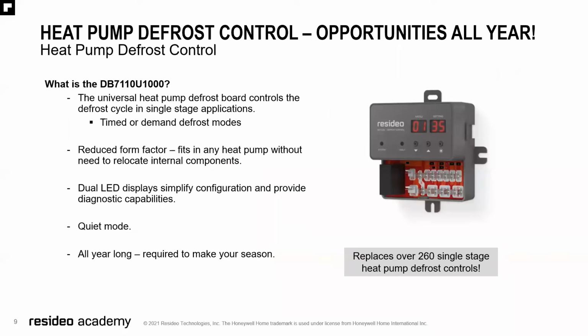Heat pump defrost control. What is the DB7110U 1000? It's a universal heat pump defrost board, controls the defrost cycle of a single stage application, can be timed or demand defrost, reduces form factor, fits in pretty much any heat pump without the need to relocate the internal components, has some LED diagnostics to simplify the configuration and to give some diagnostic capacity when you're troubleshooting a call, quiet mode, and all year long required to make your season, replaces over 260 single stage heat pump defrost controls.